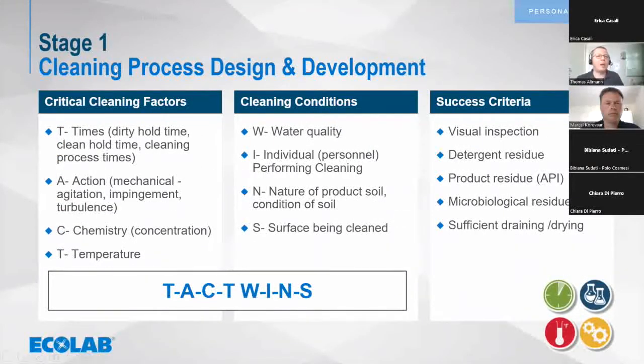Just to remind you, the cleaning process always requires some time, some mechanical action, some chemistry, and some temperature. For validation, you should identify what is driving my cleaning. Is it the long cleaning time, or more the temperature? Is it more the chemistry? Do I have to make sure that I dose the chemistry correctly, up to a good percentage?